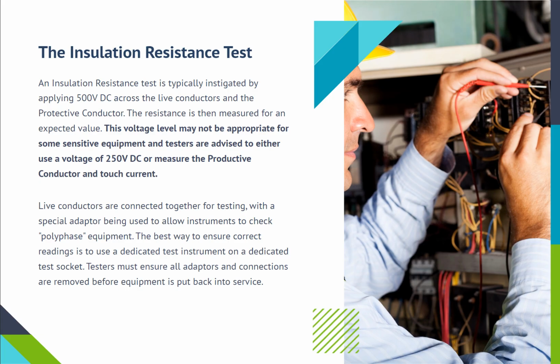Live conductors are connected together for testing, with a special adapter being used to allow instruments to check polyphase equipment. The best way to ensure correct readings is to use a dedicated test instrument on a dedicated test socket. Testers must ensure all adapters and connections are removed before equipment is put back into service.